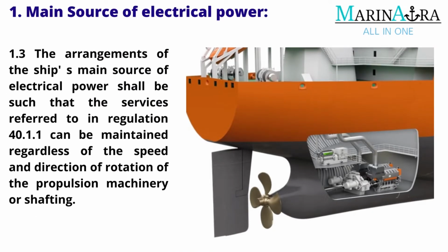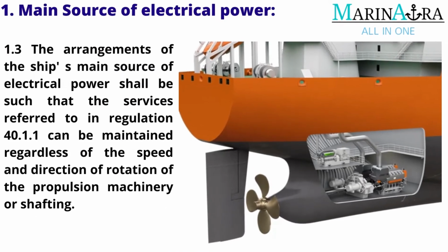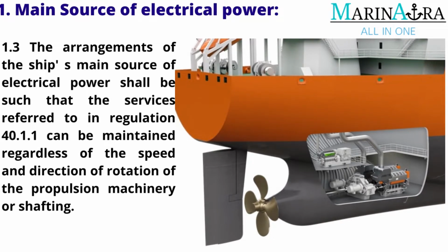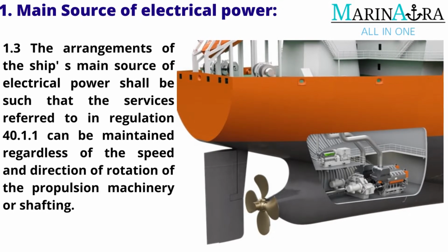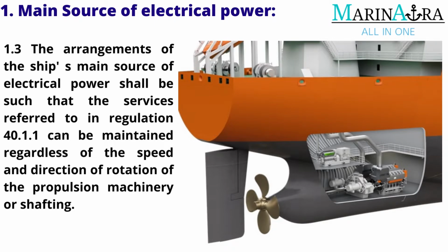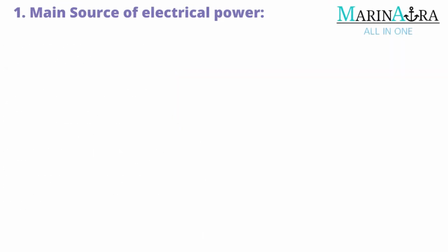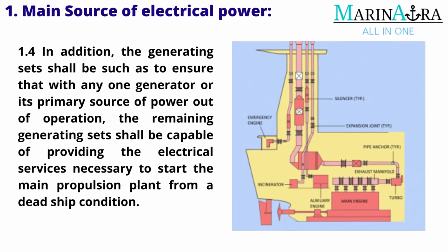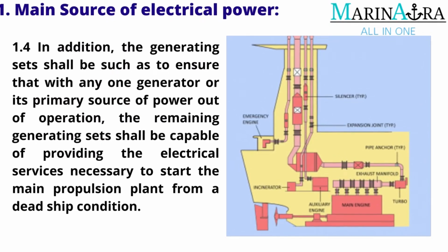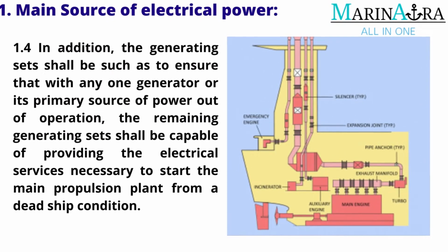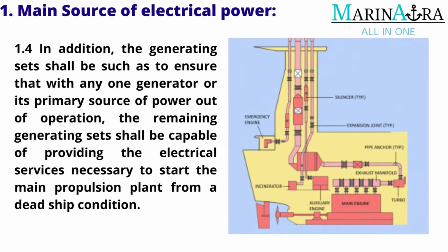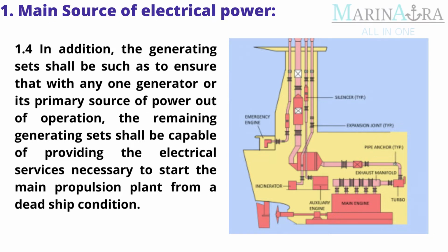The arrangements of the ship's main source of electrical power shall be such that the services referred to in Regulation 40.1.1 can be maintained regardless of the speed and direction of rotation of the propulsion machinery or shafting. In addition, the generating sets shall be such as to ensure that with any one generator or its primary source of power out of operation, the remaining generating sets shall be capable of providing the electrical services necessary to start the main propulsion plant from a dead ship condition.